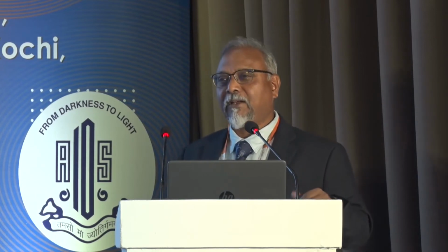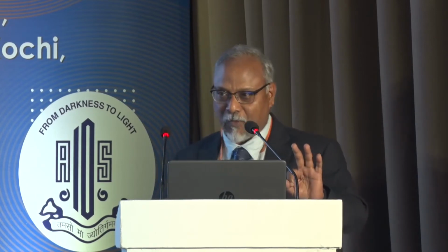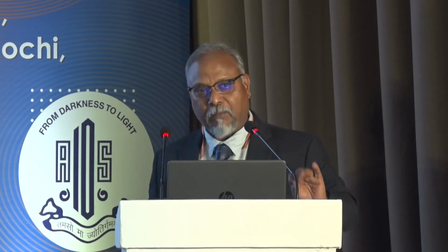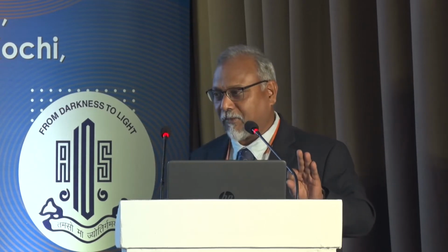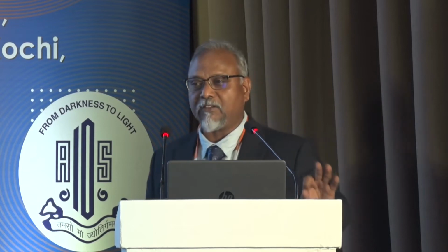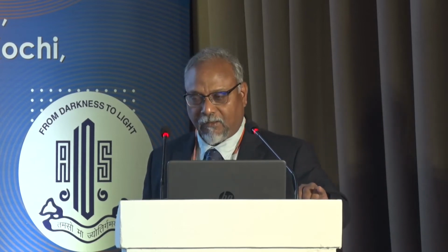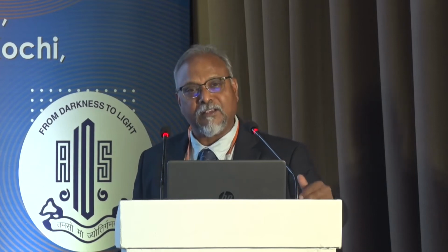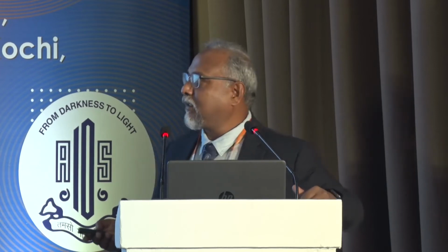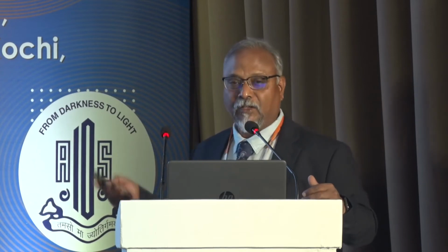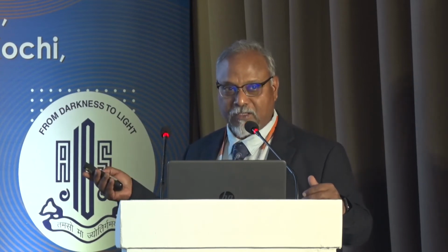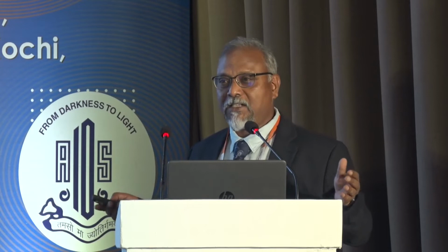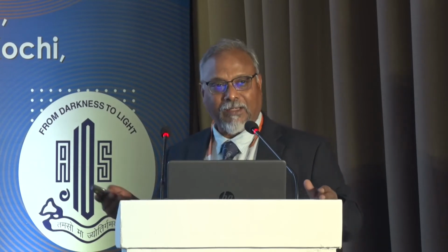The diffractive technology does three things. One, it splits the light, it partitions the light, and it bends the light. Okay, all functions of them depend on these three things. It splits the light, it partitions the light. Partition means for distance and near, and trifocal with distance, intermediate, and near. And this is determined, the partitioning is determined by the height of the ridge. You have multiple ridges, this is called a kinoform. The partitioning is determined by the height of the ridges.